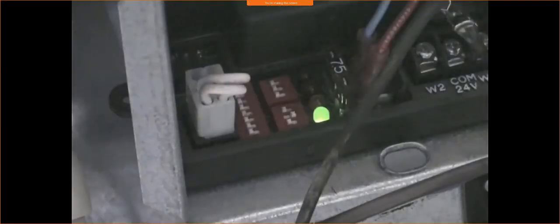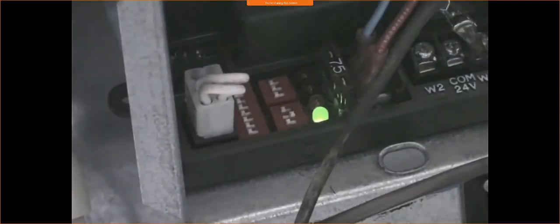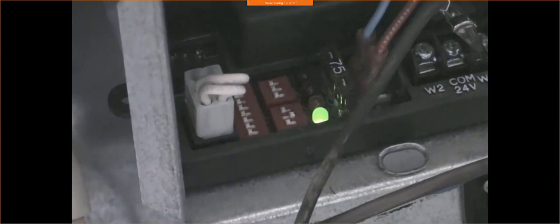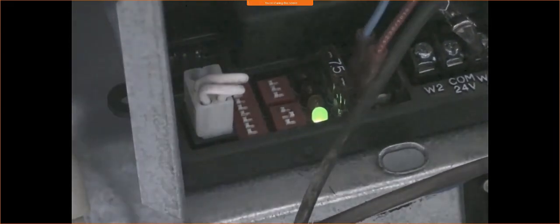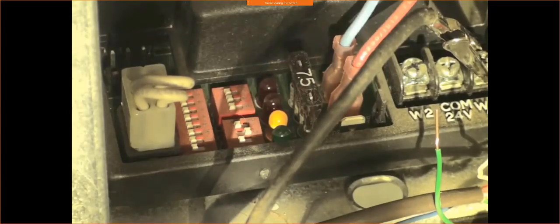Okay, that's your indication of first stage heat, everything normal. The light just stays on. Second stage heat, the yellow light goes on. That's that one right up there. Okay, this code is for high limit. It's a 33. There's 3 flashes with each of the 2 lights. It means a limit switch is open, plugged filter, plugged blower wheel, duct problem, or possibly a rollout switch open from the flame rolling out the front. So that's a high temp limit code.